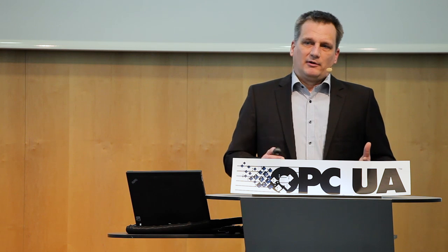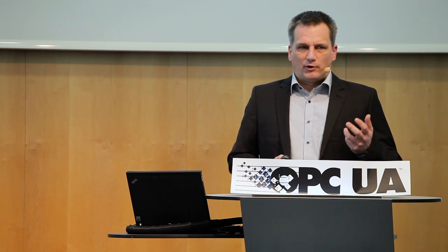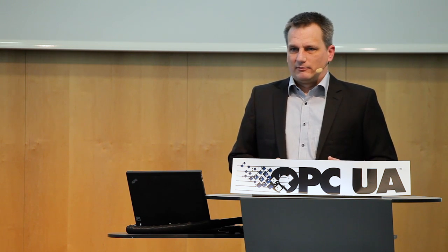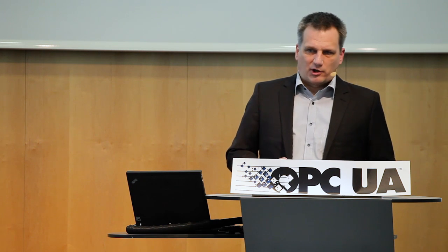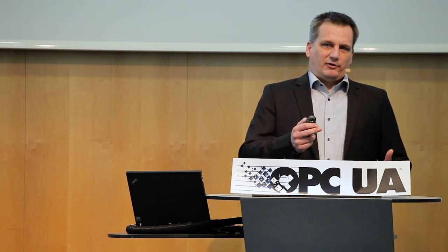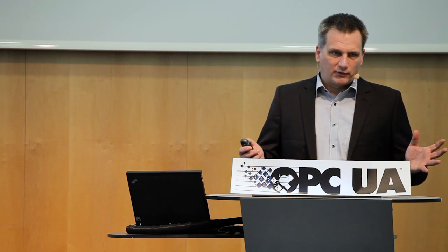to that type, and it now can show all different instances of measurements, no matter if it's a temperature or pressure or whatever. So we have faceplates, graphical displays that belong to types, and by this, the engineering can be reduced immensely, because we just need to connect the type once, and then everything else gets connected automatically. So the engineering is much, much faster.